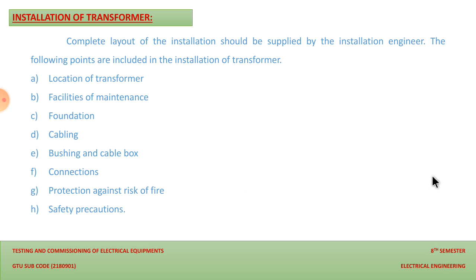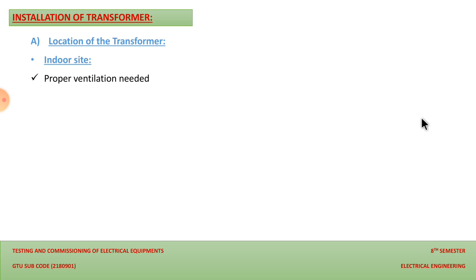So these are the points that we should keep in mind while we are installing a transformer at the premises. Let us discuss these points in detail. Location of the transformer. If you need to install a transformer at an indoor site, proper ventilation is needed, because if the transformer is installed inside, after certain use it will get heated up, and due to the heat the inner temperature of the transformer oil will increase. So we need to provide proper ventilation as per the Indian standard rules.